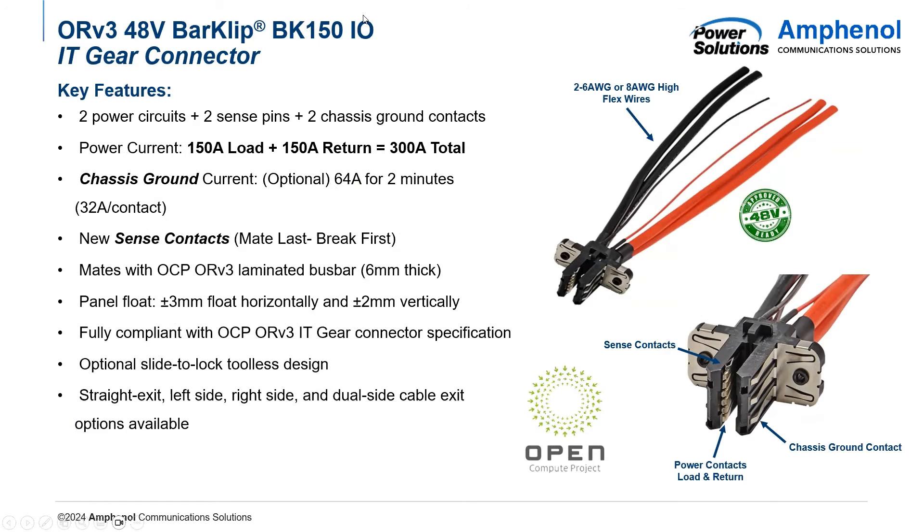Lastly, we have our BK150 IO — the IT gear connector, which connects to the payload shelves. This features two power circuits, just like the BK500, and also two chassis ground contacts rated for 64 amps for up to two minutes. It also features two sense pins, which are brand new. These sense pins work in tandem with the system's intelligence and can detect if power is being unplugged while current is still flowing. They are featured lower in the connector, so they break first whenever being unmated. If the system intelligence senses that the bus bar is still powered when it's being disconnected, it will cut power to the connector, meaning that it won't have any arcing. Arcing, especially for DC power, can cause a lot of damage to the connector, so these sense contacts try to avoid as much damage as possible.